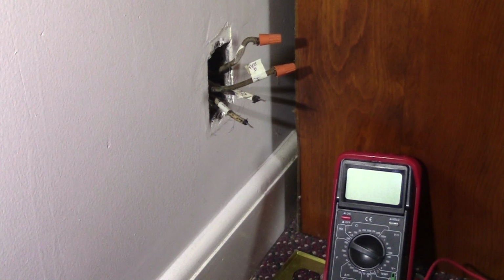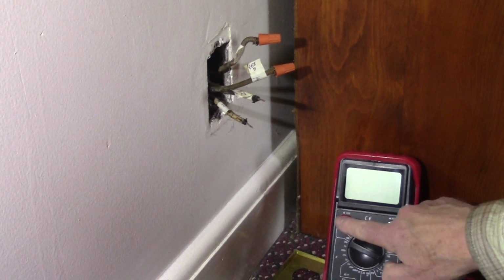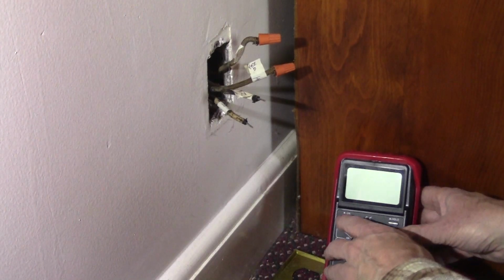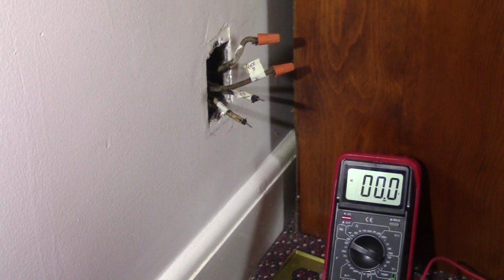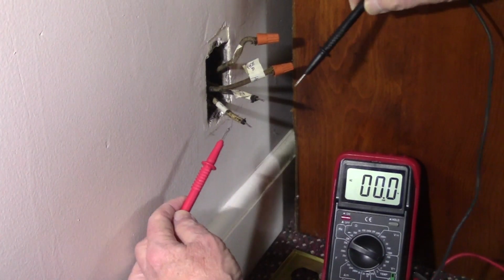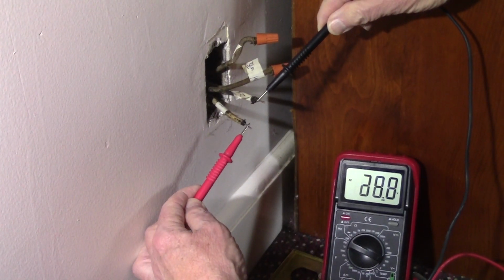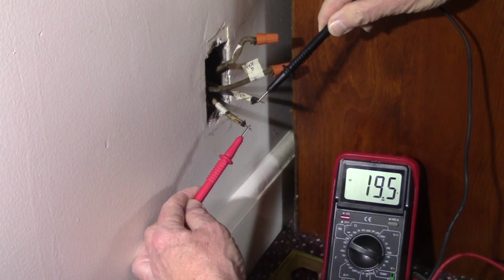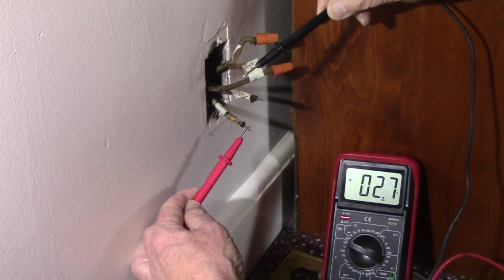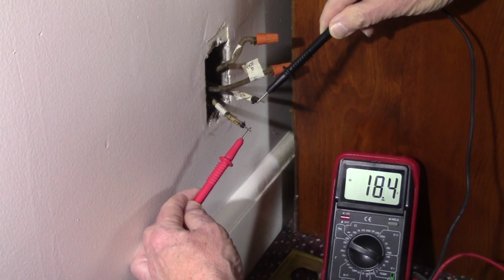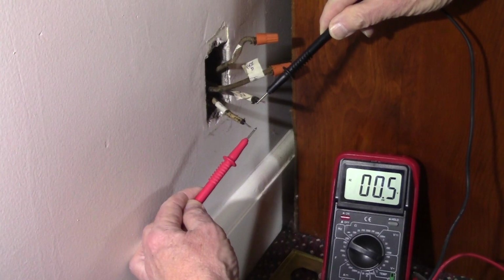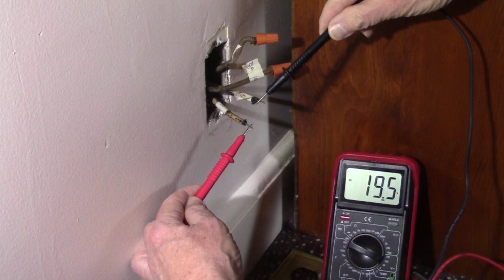Hey guys, have you ever turned off a circuit breaker and measured the voltage just to be sure it was off, expecting to see zero, but instead seeing 5, 10, 15, or even 30 or 40 volts? If so, you may have seen what some electricians call a phantom or ghost voltage. They call it that because they believe that somehow it really isn't there.